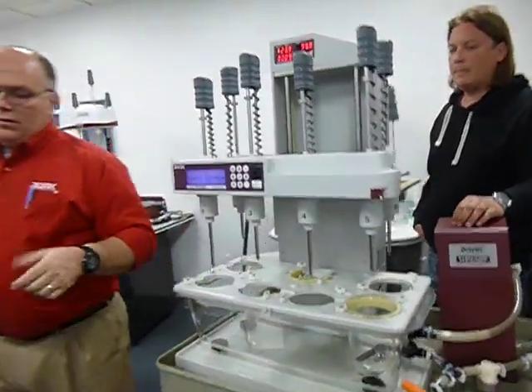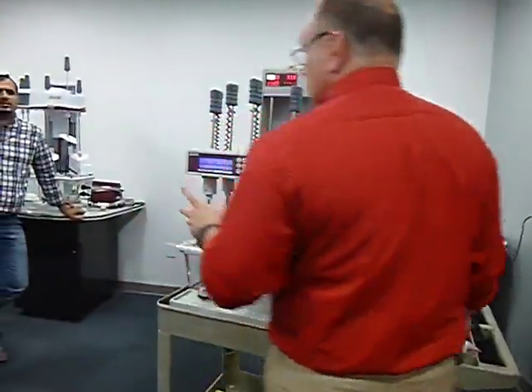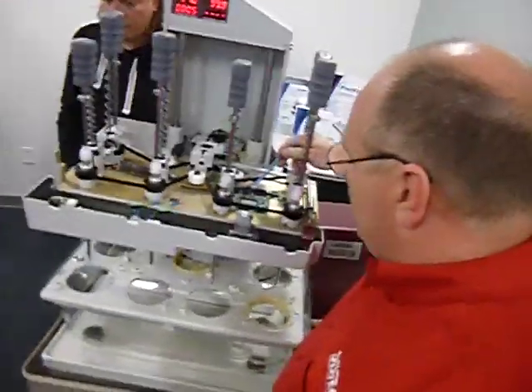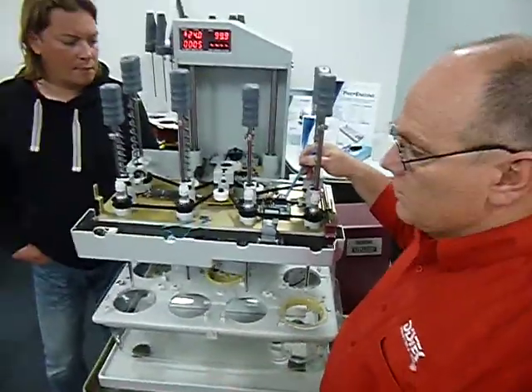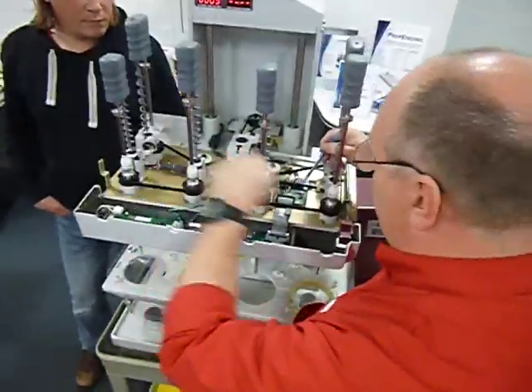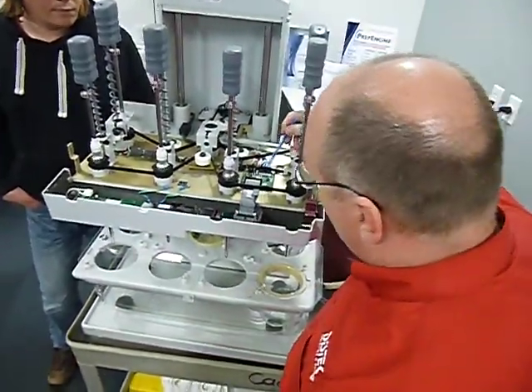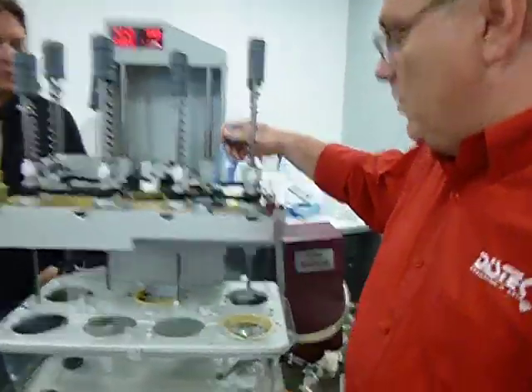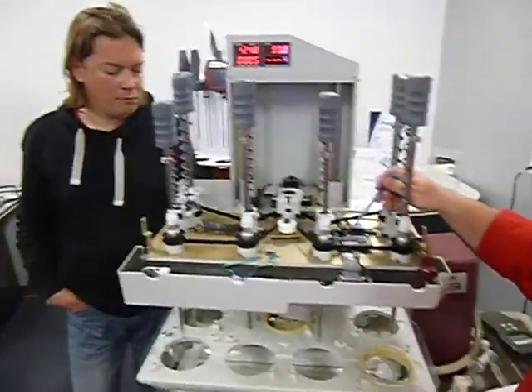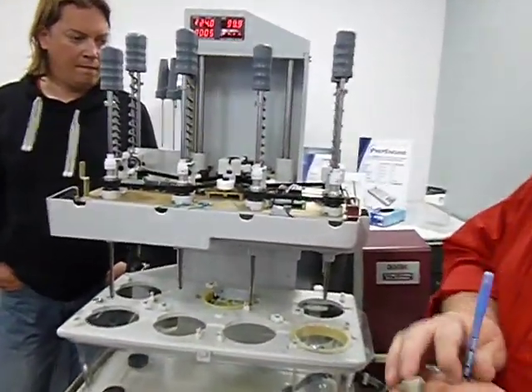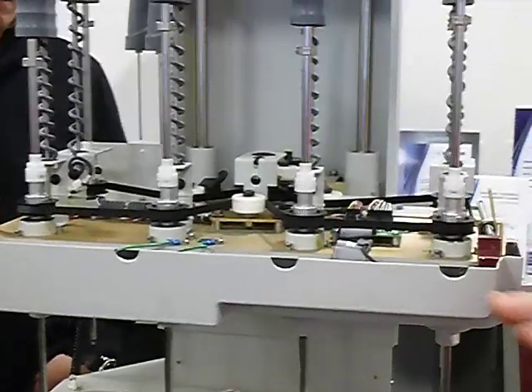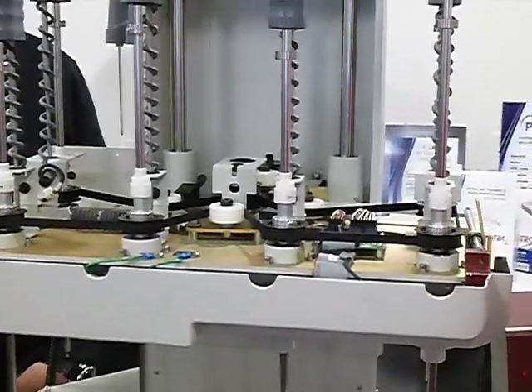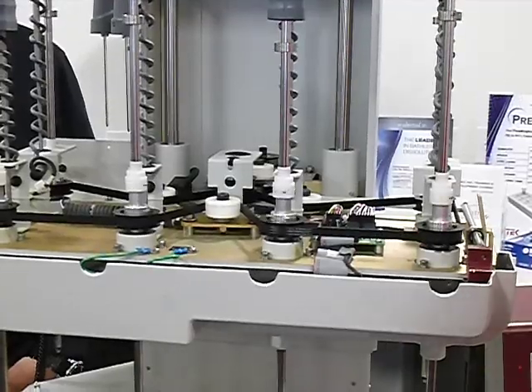A lot of times, troubleshooting wise, and this is a good troubleshooting point, on the board here, I've got everything running, so I don't want to take anything apart. But these right here are all your wires going to every one of the RTDs. This is the first one, two is the second set, third, fourth, the fifth, and sixth on this connector right here. And the red, black, and white wires over here at the end are the ones going out to this probe here. Sometimes these pins have a tendency to unlock and push back a little bit and not make really good contact. And that could be a source of temperature fluctuations also. So that would also be something that you might want to check.